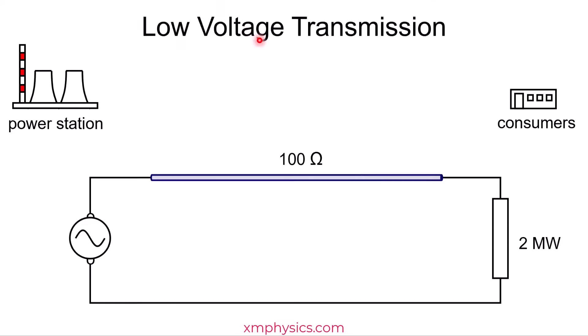Now see what happens if we use low voltage transmission instead. So if we use a relatively low voltage of 20 kilovolts, then we require a relatively high current of 100 amps. Now we have 100 amps running through these 100 ohms. The power loss is, tada, 1 megawatt, which is unacceptable compared to 2 megawatts.